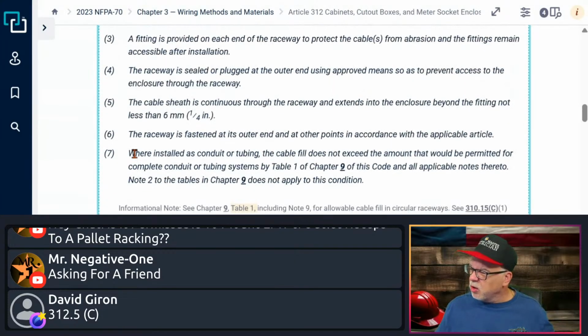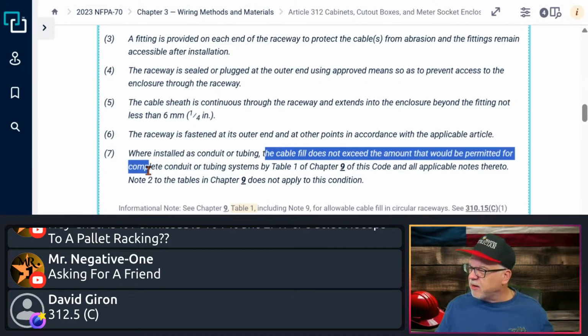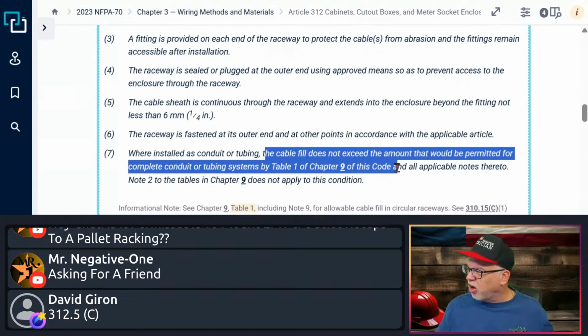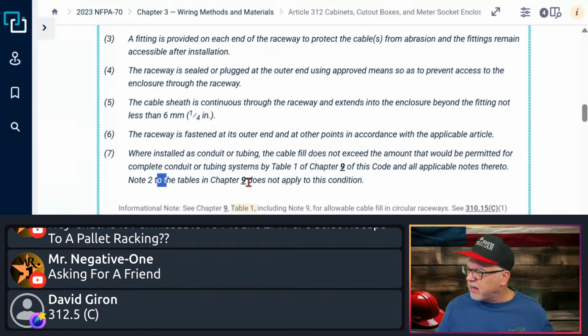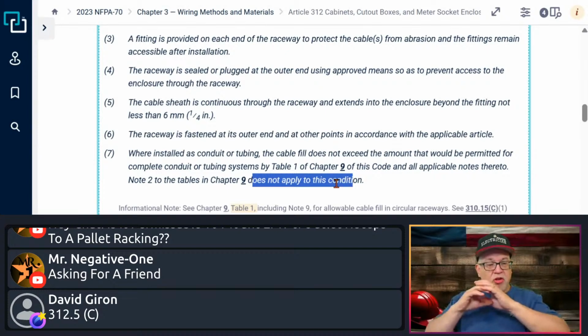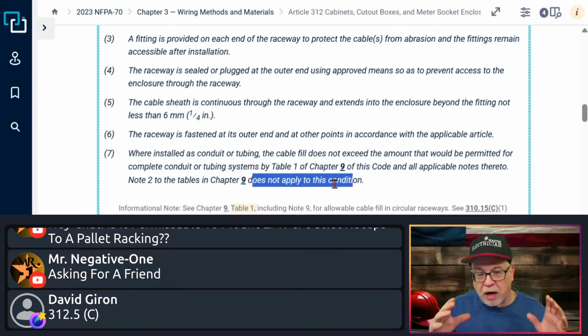And then it says, or installed as conduit or tubing, the cable fill does not exceed the amount that would be permitted for a complete conduit or tubing by Table 1, Chapter 9 of this code, and all applicable notes thereto. Note 2 of this table in Chapter 9 does not apply to this condition. So you still have fill requirements if you're going to do this.